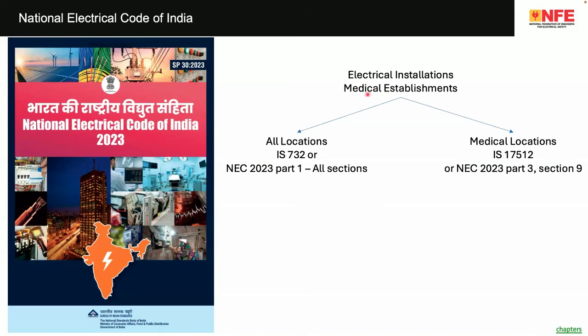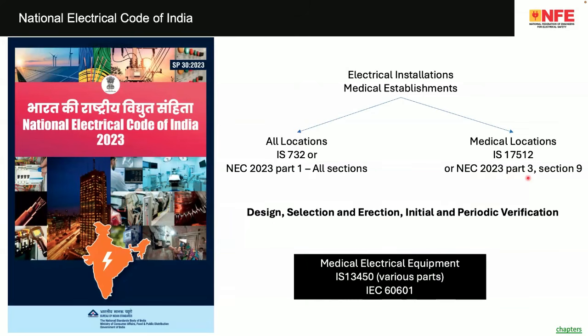Now, how does this standard explain? For medical establishments there are 2 safety measures required. All the locations in the hospital should comply with National Electrical Code 2023 Part 1, all sections, and medical locations need additional safety measures, which are explained in Part 3, Section 9. Here we are talking about the design, selection, erection, initial and periodic verification of the installation. Please note, when I say installation, it is not the biomedical equipment. It is not an equipment which you are using. It is about the selection of the conductors, selection of protective device, how you are installing the wirings, how you are routing the wires, how you are fixing the wires, what is the rating of the wire, what is the rating of the protective device, and so on. So design, selection and erection, initial and periodic verification.